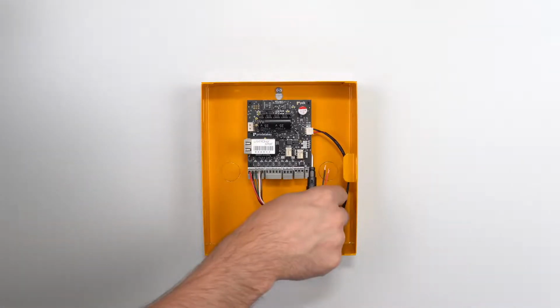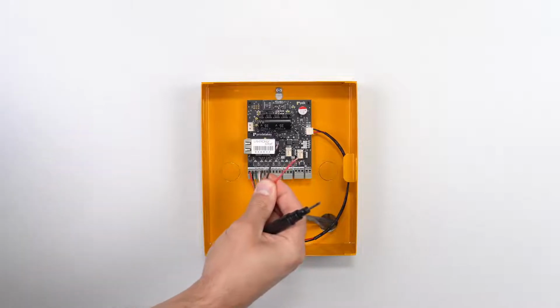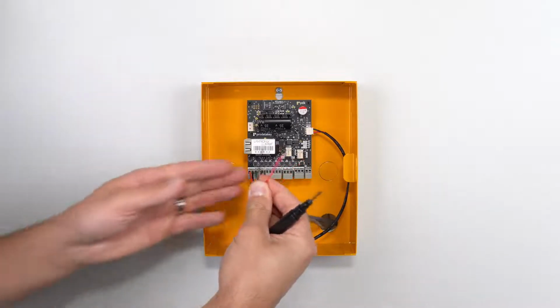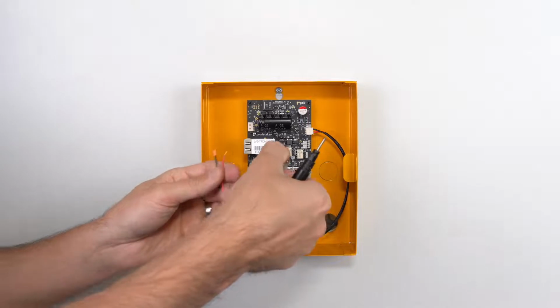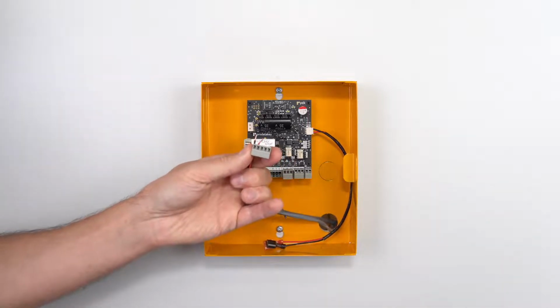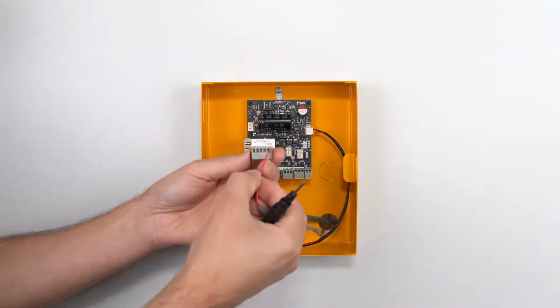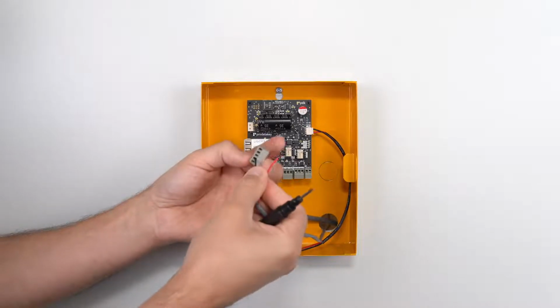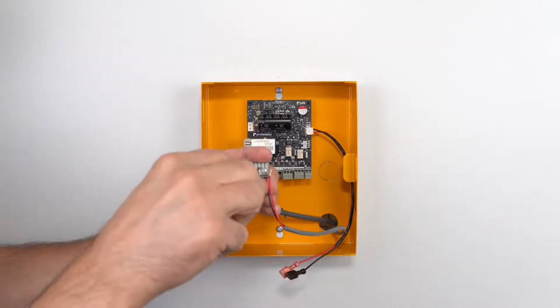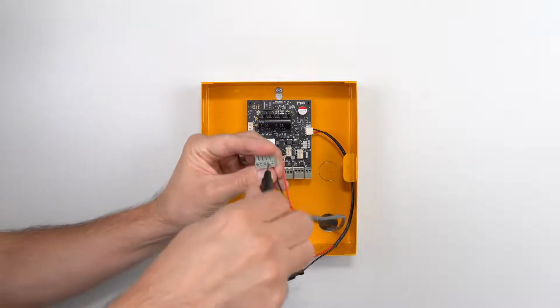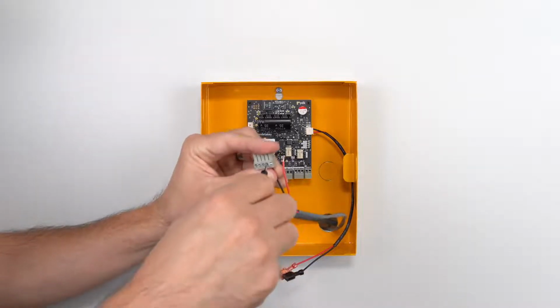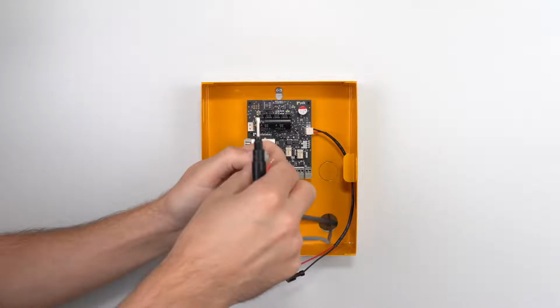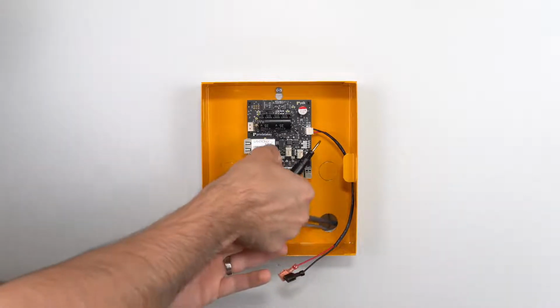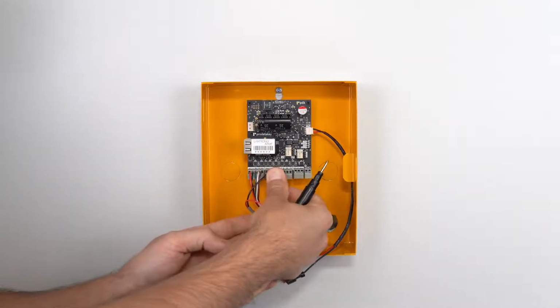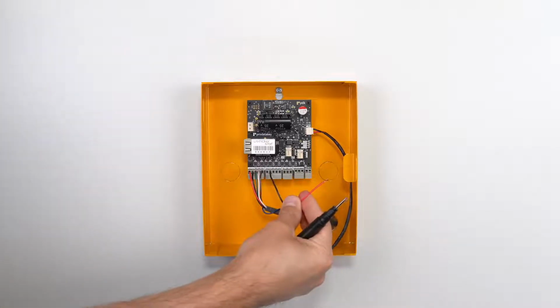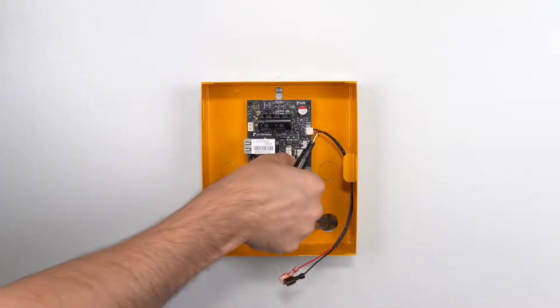So on a DPS wire, you're going to find it's typically a red and a black wire. It's very typical. There's not a positive and a negative, although you will tie one side of the DPS into negative for PDK. Other types of controllers may handle this a little bit differently, but for most of them it's just providing a ground loop based on whether that door is open or closed. So if you look at a door position sensor, it's a security contact, and it just has a little reed in there.